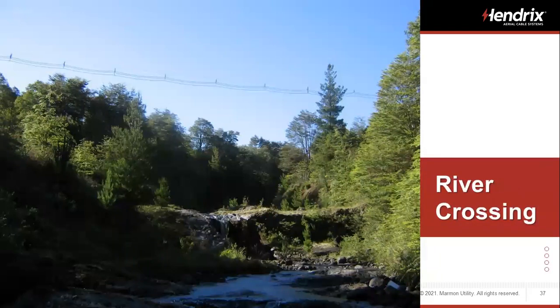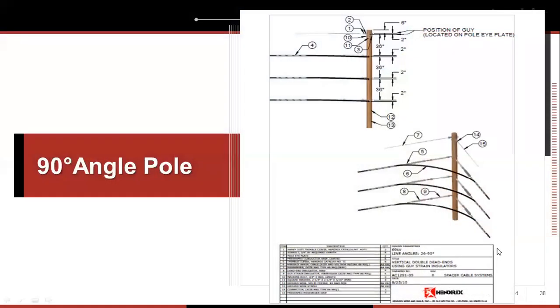This is a river crossing. It happens to be an inaccessible river crossing. This is a river for lava when there is lava. So that's nice. Here's a 90-degree angle pole. We're basically dead ending the cables on both sides, running them right through the preformed dead end grips without cutting or opening the cable.